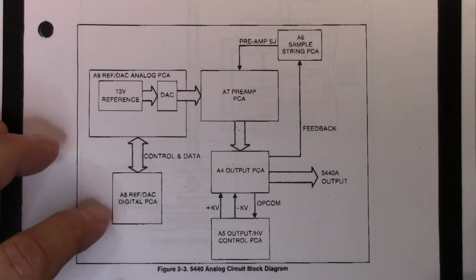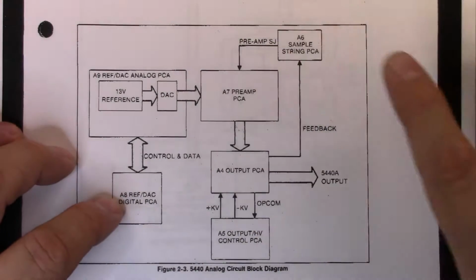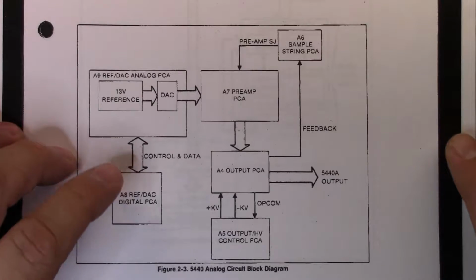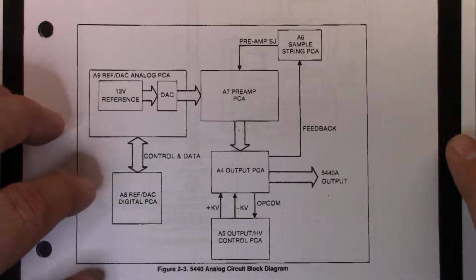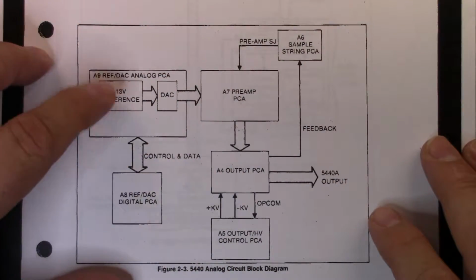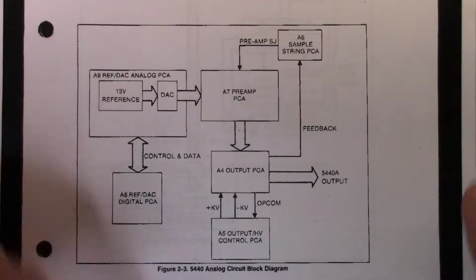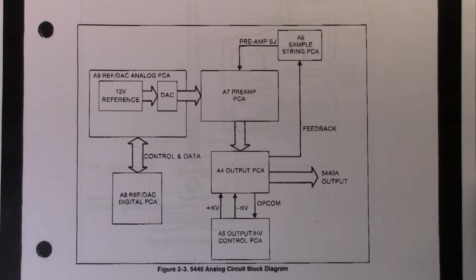I'm going to come in and set some voltage, and that voltage is going to control what is actually done in the output stages. The system here uses a 13 volt reference. There's been a great thread on the EEVblog, I'll link it below, about whether these are artifact calibrated or not. Somebody did a 10 volt calibration against the internal 13 volt reference and found that yes, these appear to be artifact calibratable.